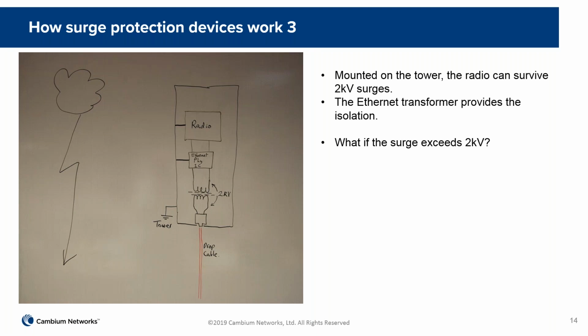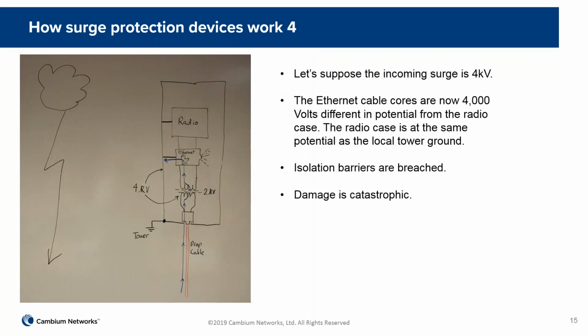But we're not in control of how near that lightning strike is, or whether indeed the tower itself is hit. And so we need to add some external protection to assist. So if we did have a strike nearby to the tower, then we would end up with perhaps not 2 kilovolts, but 4 kilovolts, and the current would flow up the drop cable. It would flow across the isolation boundary, because that is only capable of withstanding 2 kilovolts, and we have a 4 kilovolt surge, and it then flows into the Ethernet PHY in this instance.